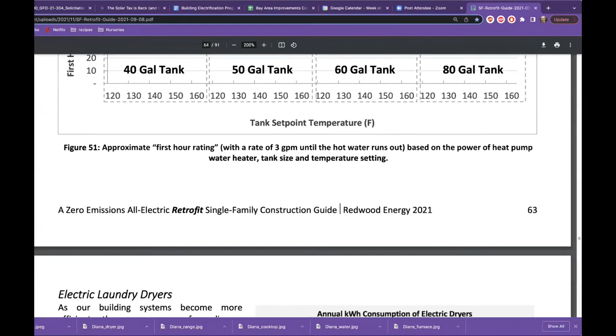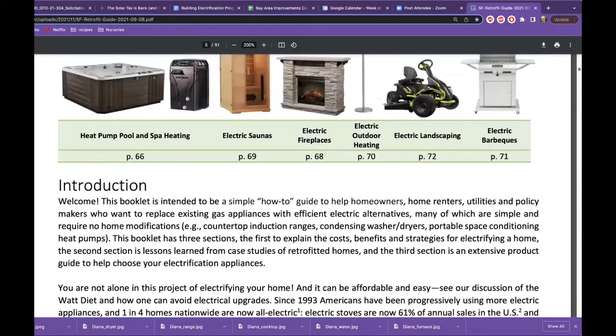Yeah, so the way the panel sizing works with solar and electrification is that you can basically size solar to be about 20% as big as the main panel rating. So you could backfeed solar into a 100 amp panel on a 20 amp breaker. And lots of inverters are sized to supply that 3.8 kilowatts that is allowed to flow on the 20 amp breaker. This is an example that Tom made of a panel like this that has a 20 amp solar array, but this is a 100 amp panel.